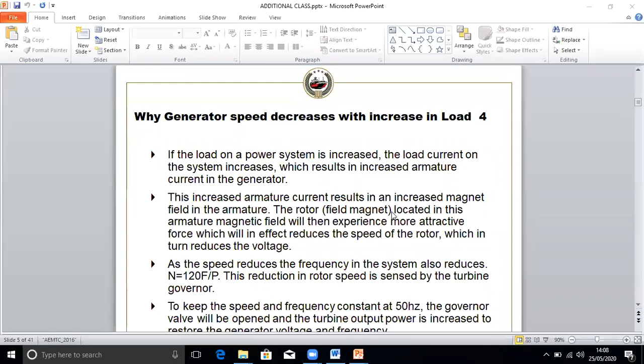This droop setting, the droop speed, is a drop in speed. Droop means a drop in speed with the load. It's a characteristic of a governor or speed regulator of the engine. So when used as a standalone generator, this will determine the drop in frequency. Here you can see 2 to 4% of the full load.